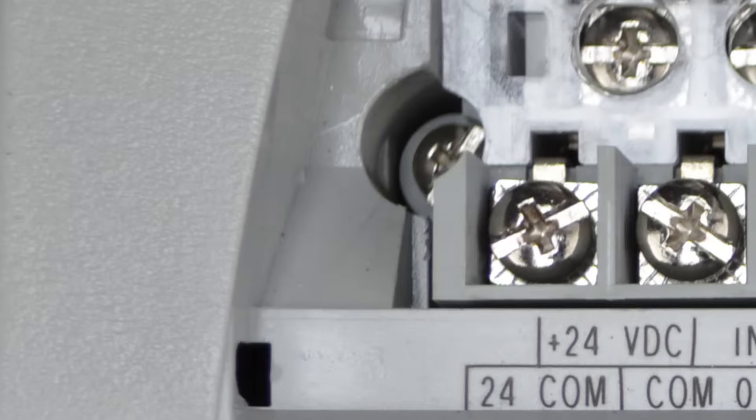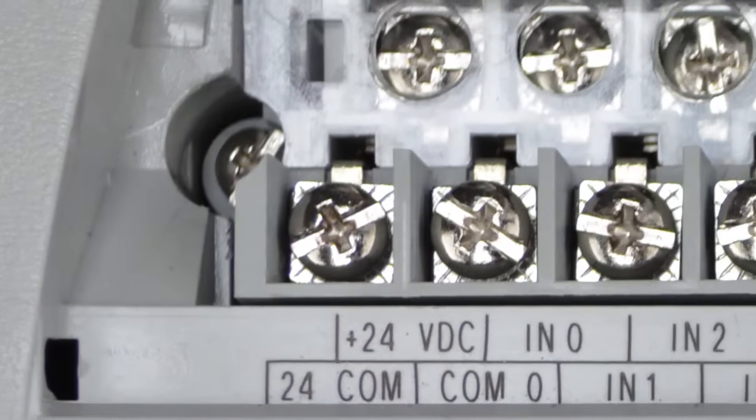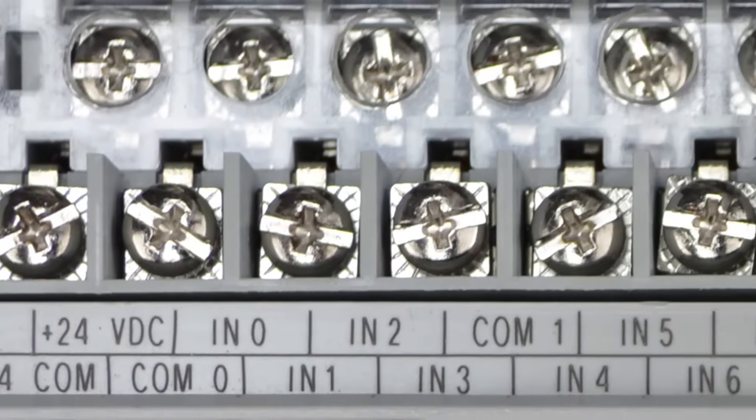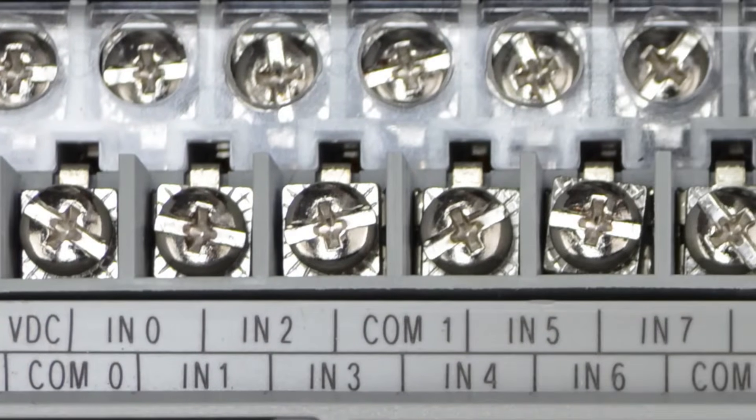Now this power source is often referred to as sensor power, and it should only be used for the input circuits. Moving to the right, we see our first four inputs share COM0, which means they all need to share a common power source.